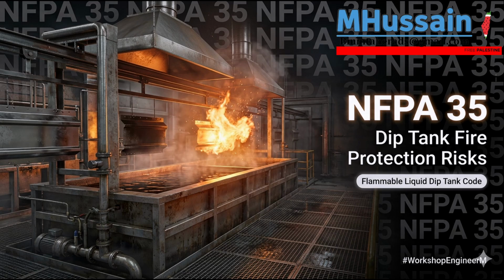Yeah, so if you are the layout engineer trying to fit massive process vessels into a tight site plan while designing the fire protection, or if you're the mechanical contractor actually putting the pipes and pumps together, or even if you are the facility owner whose livelihood depends on maintaining this operation safely day in and day out, this is your shortcut, because we are looking at materials where, honestly, a single design flaw can lead to an absolute catastrophe. And what becomes immediately apparent when you really study this standard is that it isn't just some arbitrary list of bureaucratic red tape. Oh, definitely not. It's an incredibly intricate, holistic system of physics, chemistry, thermodynamics, and risk management.